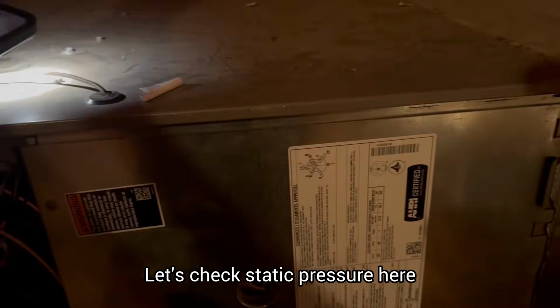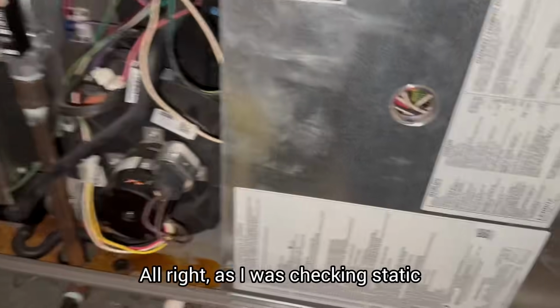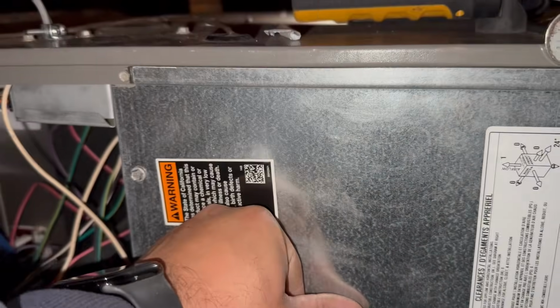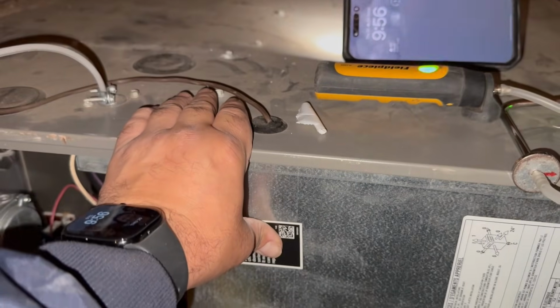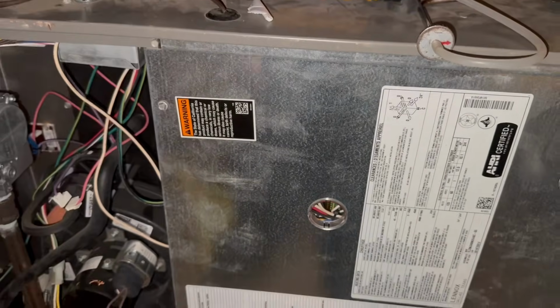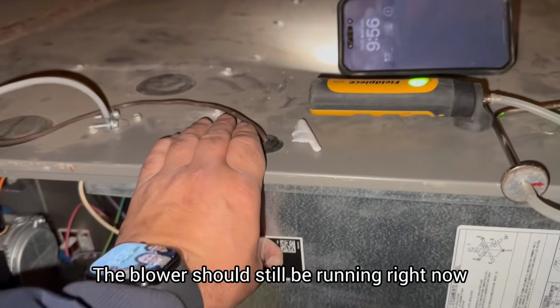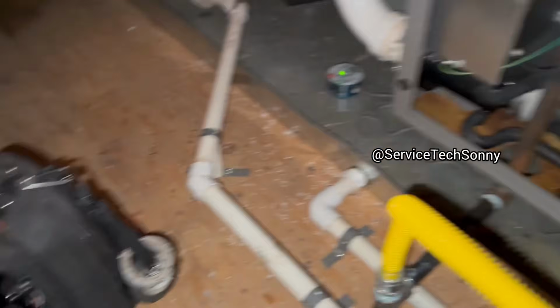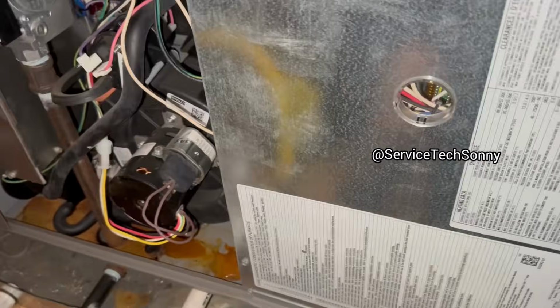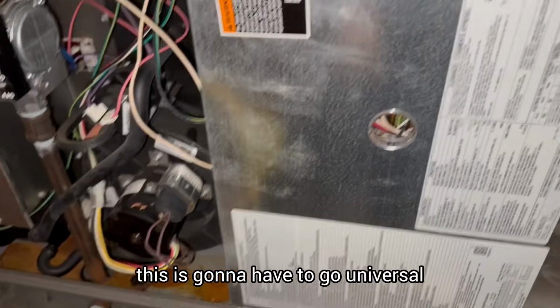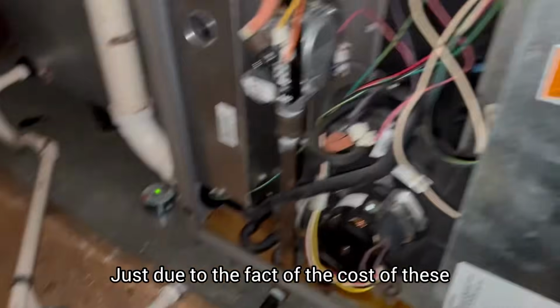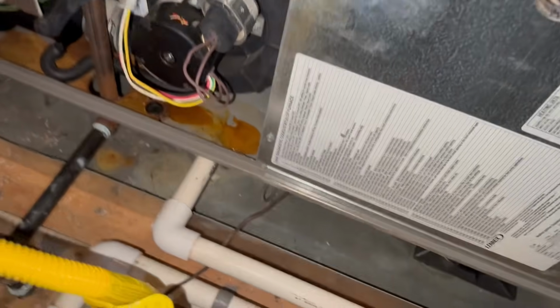Let's check static pressure here. All right, as I was checking static, we hit a limit. No blower motor, guys. No blower motor. The blower should still be running right now. Let's pop it open. Damn, a Lennox ECM motor. This is gonna have to go universal, just due to the cost of these damn things for Lennox, man.